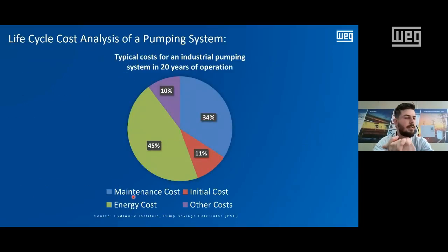So even though you are not in the European Union and you're possibly thinking, why should I be more efficient? The first thing to think about is that when you are more efficient, you are definitely going to impact less the environment that you are in. A second very important point is that if you analyze the life cycle cost of a typical pumping system over 20 years of operation, you will see that the energy costs will account for about 45% of the total costs of this system. And only 11% of the costs will be the initial costs, the costs of installing this system. So when you are more efficient, you are going to save a lot of money in the future.